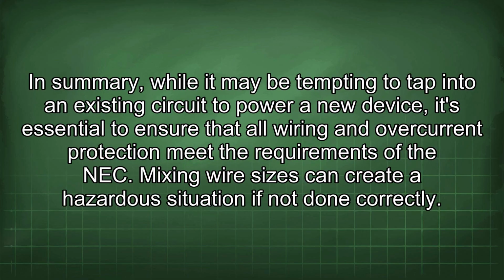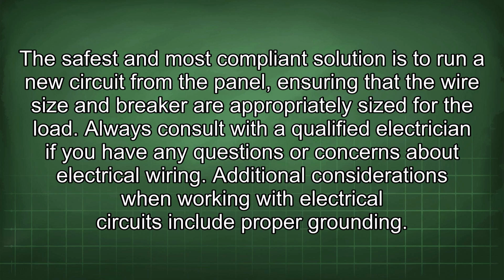In summary, while it may be tempting to tap into an existing circuit to power a new device, it's essential to ensure that all wiring and overcurrent protection meet the requirements of the NEC. Mixing wire sizes can create a hazardous situation if not done correctly. The safest and most compliant solution is to run a new circuit from the panel, ensuring that the wire size and breaker are appropriately sized for the load. Always consult with a qualified electrician if you have any questions or concerns about electrical wiring.